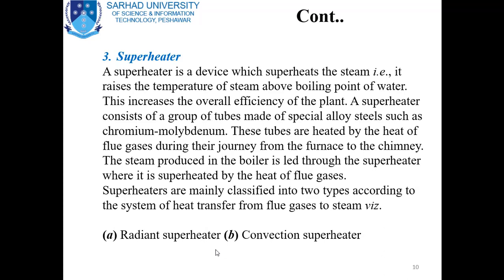A superheater is a device which superheats the steam — it raises the temperature of steam above the boiling point of water. This increases the overall efficiency of the plant. A superheater consists of a group of tubes made of special alloy steel such as chromium and molybdenum. These tubes are heated by the heat of flue gases during their journey from the furnace to the chimney. The steam produced in the boiler is led through the superheater where it is superheated.